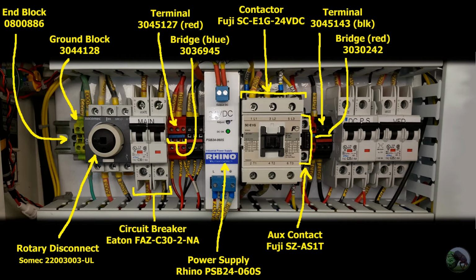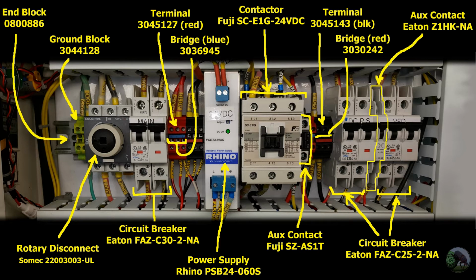And in this case, it has a red bridge, but basically does the same thing here. And then next, we have two-pole circuit breakers. And so one of these will be going to the DC power supply and the other to the VFD. And sandwiched between them, it's a little hard to see there, but I tried to highlight it, is an auxiliary contact.